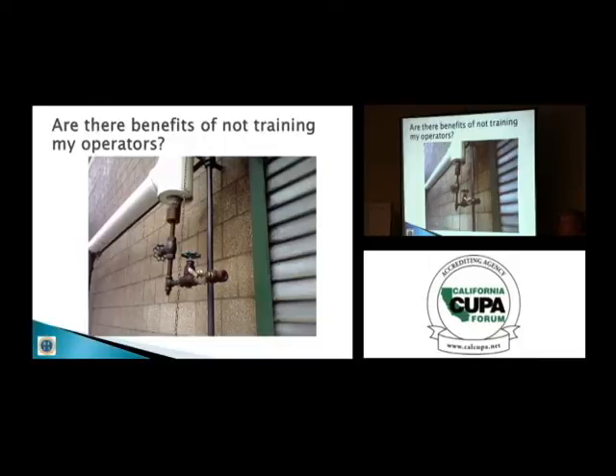We promote the use of self-closing vented valves for the oil draining. We call them dead man valves. Purpose being that when you open it, if you let go because you drop dead, the valve will close. One of the more dangerous tasks in maintaining and operating a system is the oil removal.